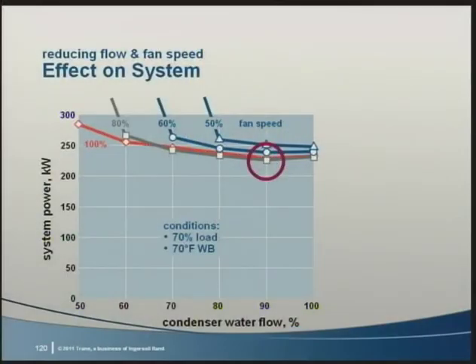But this graphic also shows another important fact. While it won't occur with positive displacement scroll and helical rotary compressors, we have to be aware of it if we attempt this on systems with centrifugal compressors. Look at the top blue line, where the cooling tower fan is operated at 50% speed. Once the water flow rate drops below 80%, the temperature of water produced by the cooling tower rises so much that it sends the chiller's compressor into surge. If you're going to reduce flow rates and tower fan speeds, do so in a manner that keeps the chiller from surging.